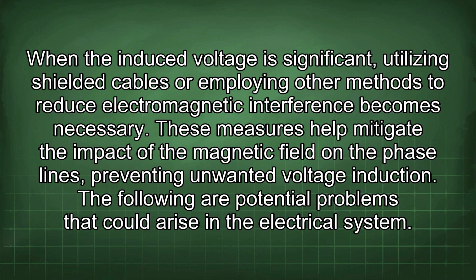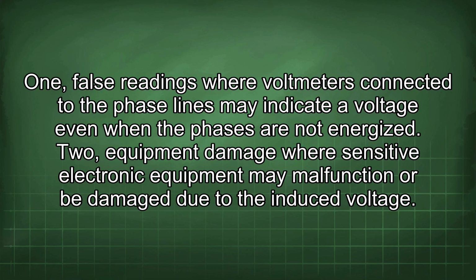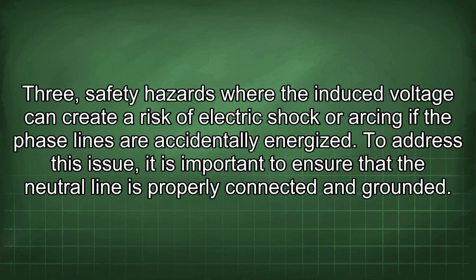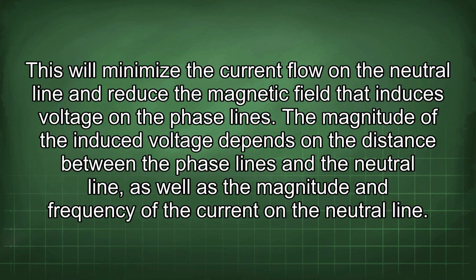The following are potential problems that could arise in the electrical system. 1. False readings, where voltmeters connected to the phase lines may indicate a voltage even when the phases are not energized. 2. Equipment damage, where sensitive electronic equipment may malfunction or be damaged due to the induced voltage. 3. Safety hazards, where the induced voltage can create a risk of electric shock or arcing if the phase lines are accidentally energized. To address this issue, it is important to ensure that the neutral line is properly connected and grounded.